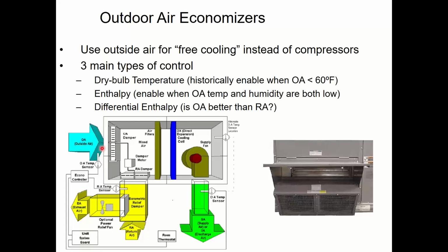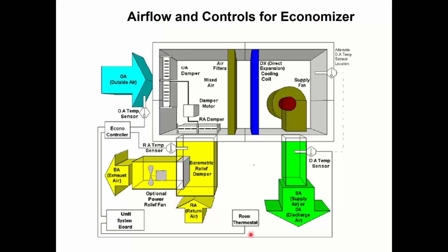Now, with 80 degree outside air, I'm still going to have to run my compressor, and we'll talk about that in a minute. But I'd rather start with 80 degree entering air than start with 85. So the way the sequence works for an economizer is the thermostat on the wall asks for cooling. He doesn't care where it comes from. He doesn't care if your compressor runs. He doesn't care if your damper opens. He doesn't care if you walk in the room with buckets of ice and blow fans on him. He wants cooling.